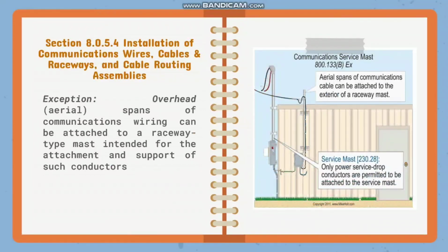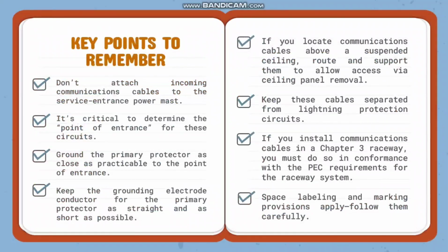So, exception po for overhead aerial span of communication cables. So, aerial spans of communications cable can be attached to the exterior of a raceway mast, but not in the service mast. Key points to remember. First, don't attach incoming communications cables to the service entrance mast. Second, it's critical to determine the point of entrance for these circuits. Third, ground the primary protector as close as practicable to the point of entrance. Fourth, keep the grounding electrode conductor for the primary protector as straight and as short as possible.